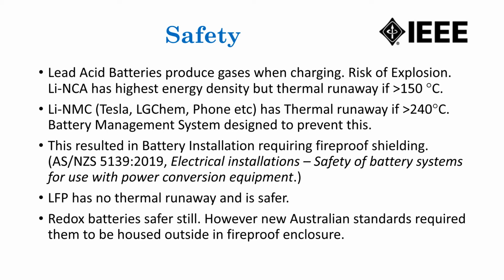Lithium nickel cobalt aluminium has got the highest energy density, but it's got thermal runaway when the battery is more than 150 degrees Celsius. Lithium nickel manganese cobalt is used in Tesla, LG Chem, and most mobile phones, with thermal runaway greater than 240 degrees C. Battery management systems are designed to prevent that.